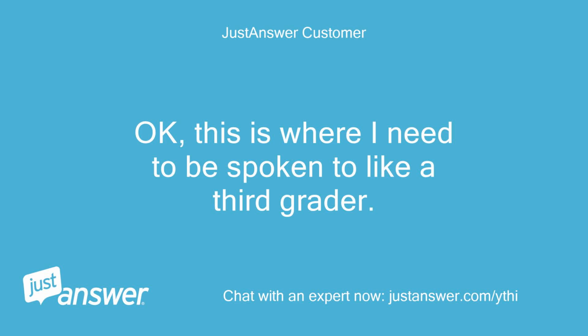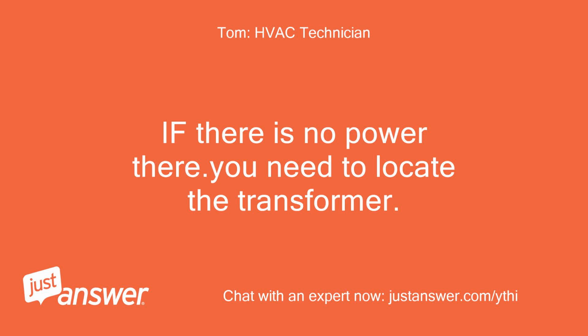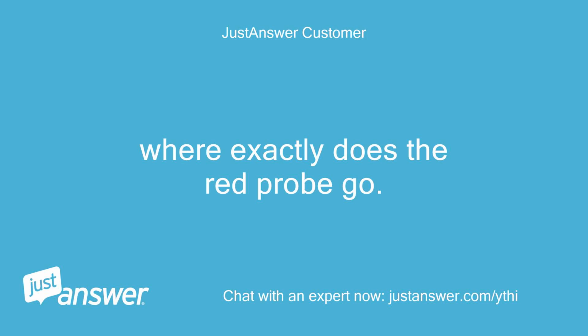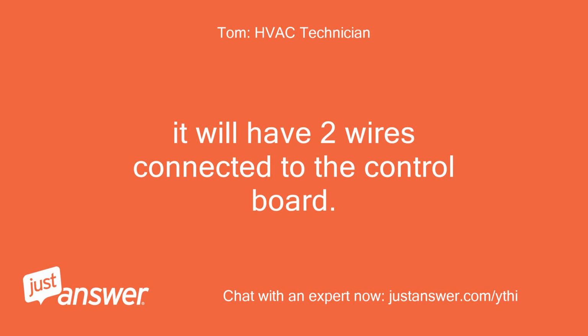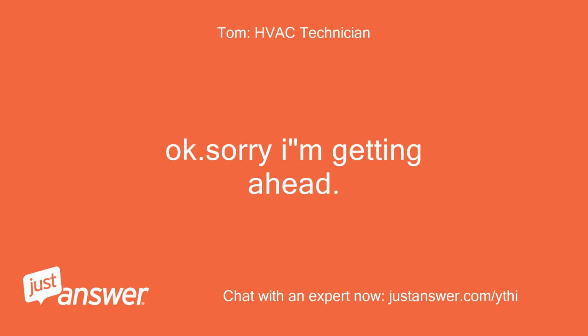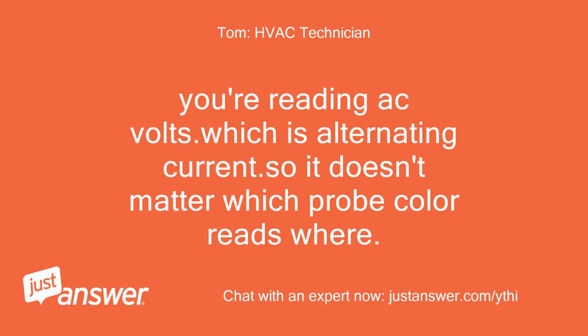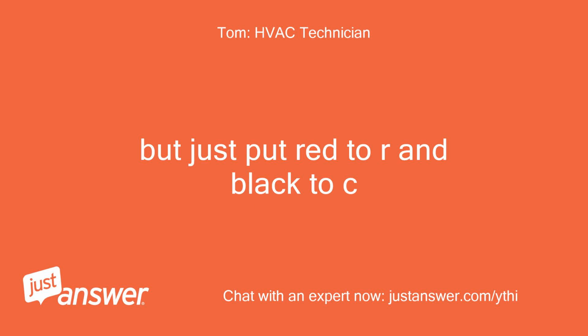Okay, this is where I need to be spoken to like a third grader. If there is no power there. You need to locate the transformer. Where exactly does the red probe go? It will have 2 wires connected to the control board. Okay. Sorry, I am getting ahead. You're reading AC volts. Which is alternating current. So it doesn't matter which probe color reads where. But just put red to R and black to C.